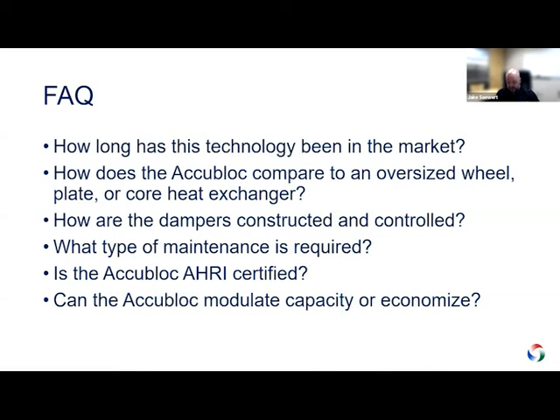Questions on the dampers. It's an industrial damper set that's manufactured by a company out of Italy. It does not use normal actuators like we have here in the United States. It actually is with a motor and a gearbox. So it's meant to flip very quickly. And it's designed for millions of cycles. So it's a little bit different technology than what we would see here, but replacement parts and things like that are still easily and readily available.